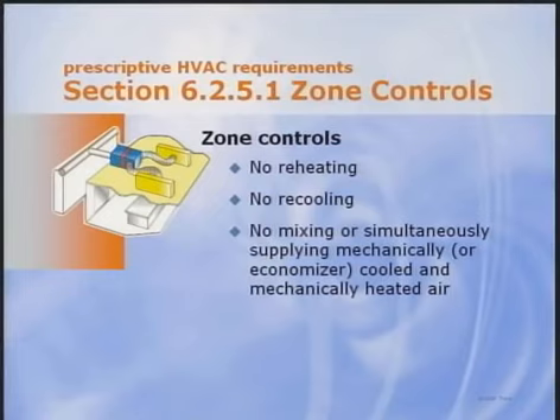Good stuff, Steve. Thanks for covering the dehumidification issues. To make this next section more understandable, we're going to change the order and cover the standard 90.1 requirements with respect to zone controls first. Often section 6.2.5.1 on zone controls is pointed to, and it's claimed that there's no way to make a VAV system comply with this section.